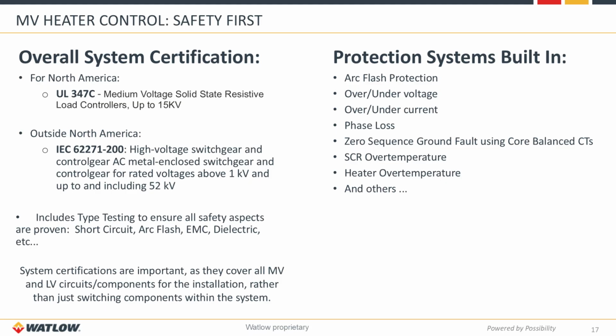Let's talk a little bit about the certifications on the panel. Obviously, safety is a big concern when it comes to medium voltage panels, and you want to ensure that the system as a whole is very safe for any operating conditions that you have. From a system level certification, for North America, UL 347C is the standard for medium voltage solid state resistive load controllers up to 15 kilovolts.